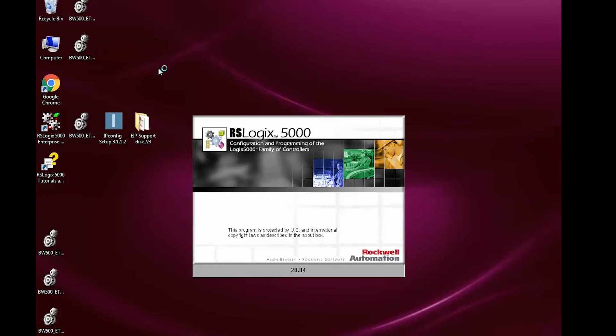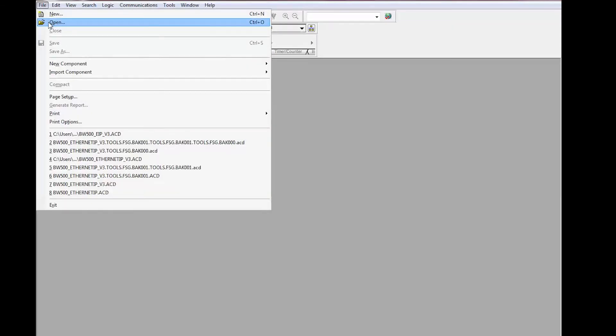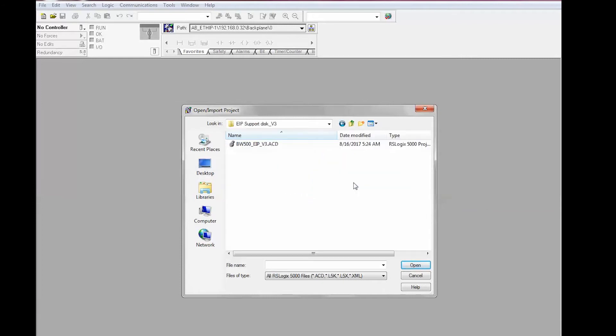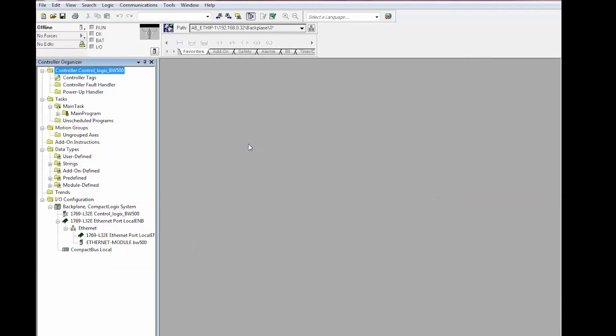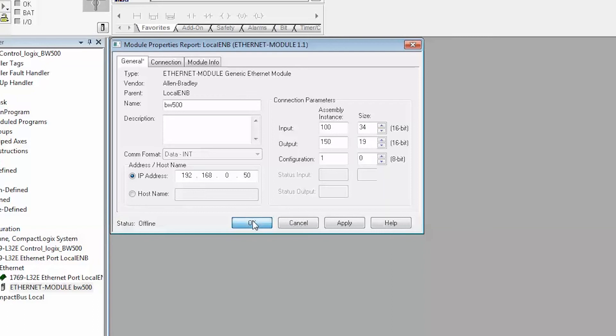Open RSLogix 5000, then go to file open. Navigate to the location on your PC where you saved the sample project. Open the sample project and navigate to I/O configuration and BW500. Click on the BW500. Enter the same IP address that you entered in the IP configuration tool. Set the input to 34 words and the output to 19 words and then click OK.